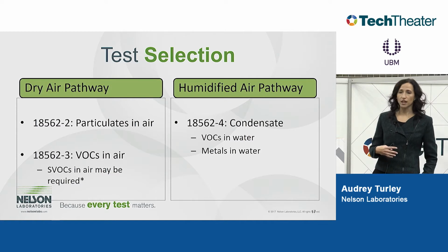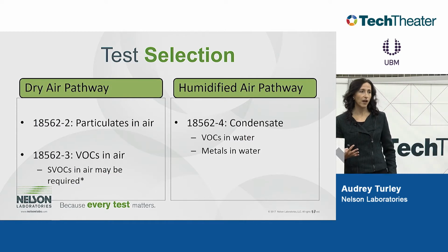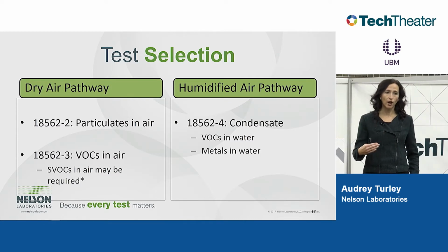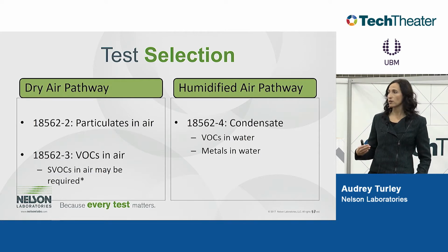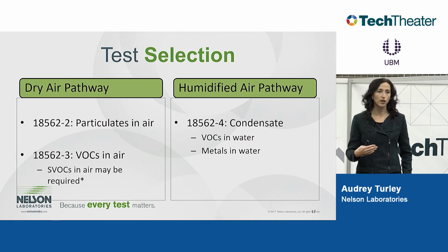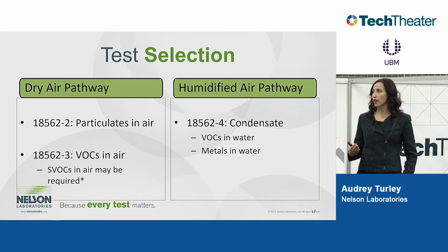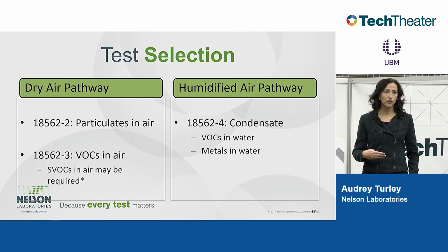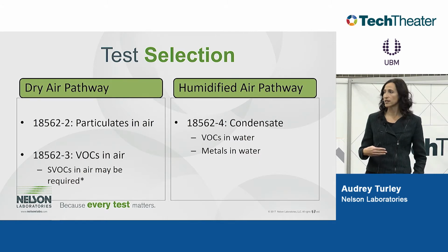We start at the beginning by identifying the use of the gas pathway devices. If you have a dry air pathway, we recommend doing particulates and VOCs—this is following part 2 and part 3. If you have a humidified air pathway, then we recommend following part 4, which is to measure your condensate.